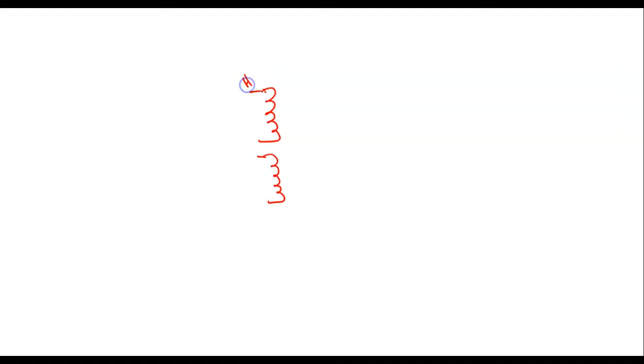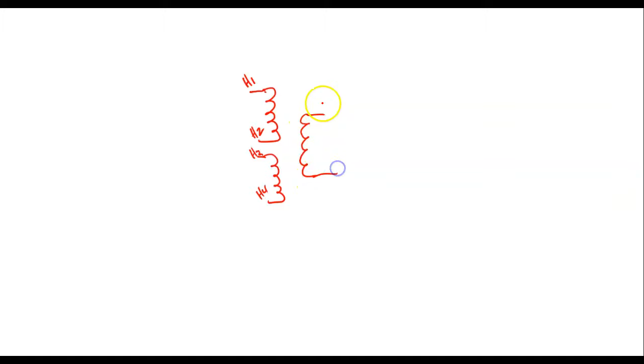This transformer is a dual winding transformer, and on the primary it's set up like this. On most transformers, especially industrial transformers, the high side is labeled with H: H1, H2, H3, H4. Then on the secondary side, transformers are labeled X, X1, X2.